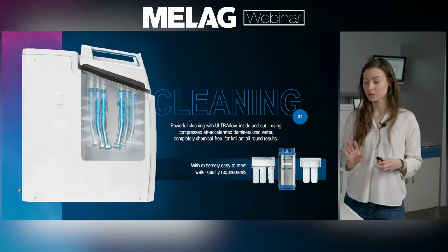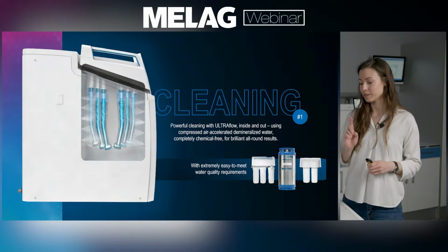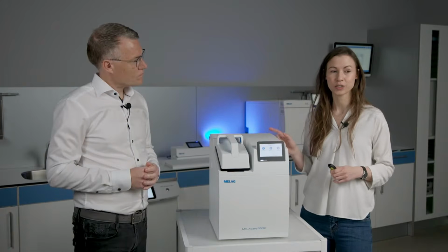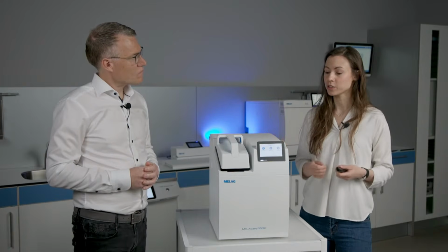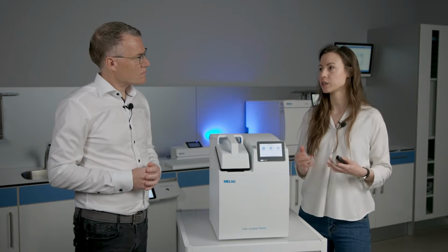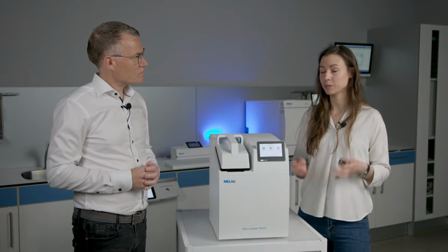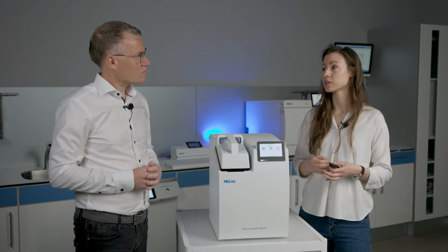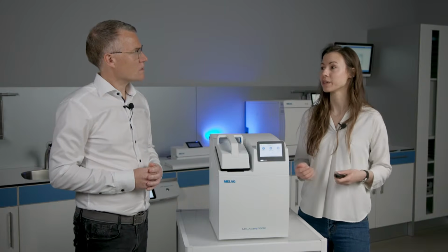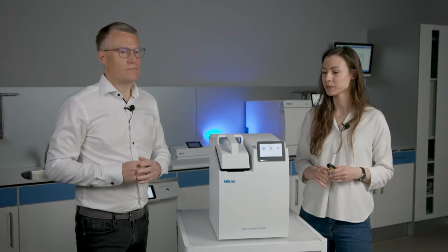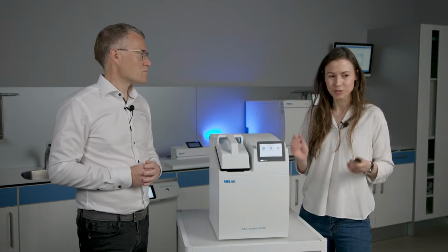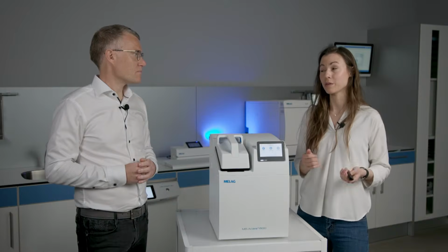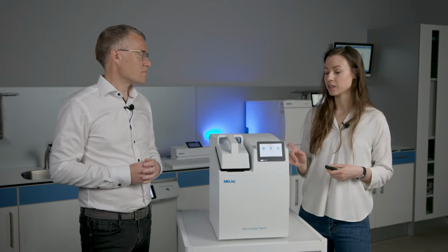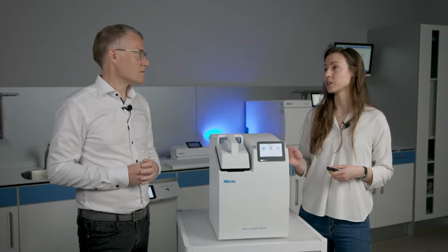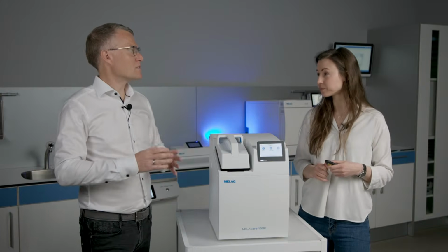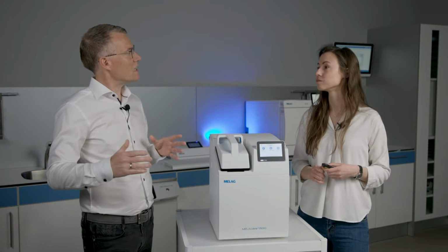Thanks to our new UltraFlow technology, the MELAG Care uses compressed air to accelerate the feed water, efficiently cleaning the inside and outside of the instruments completely without any additional chemicals — no cleaning agents are required, making it chemical-free. As with our other MELAG devices, this device has a high tolerance for feed water quality, meaning the filter of a water treatment system will last longer.